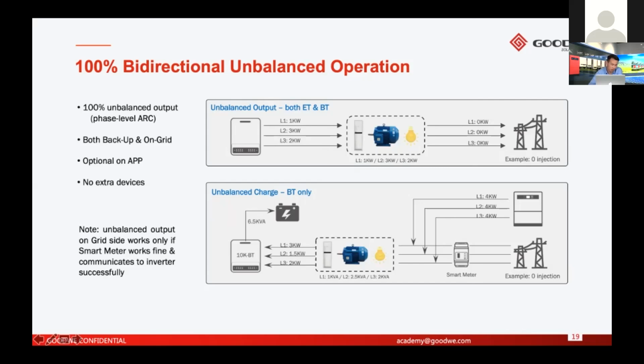Because normally for three-phase solar inverters, on the AC side, the three-phase output, on each phase, the output must be the same. But for ET and BT, we have a breakthrough on the technologies, so it can realize unbalanced output functions. This function is very important for some places that need zero export function, because the solar production cannot be exported to the grid.